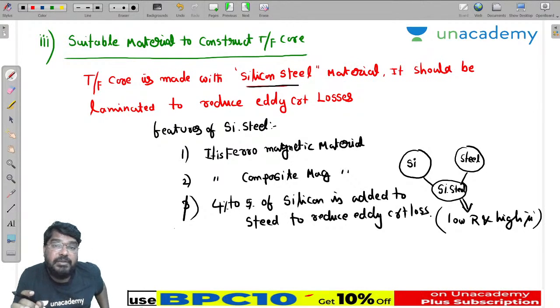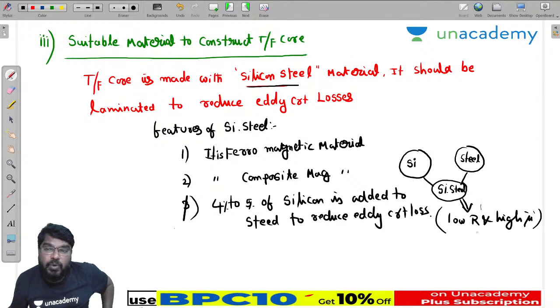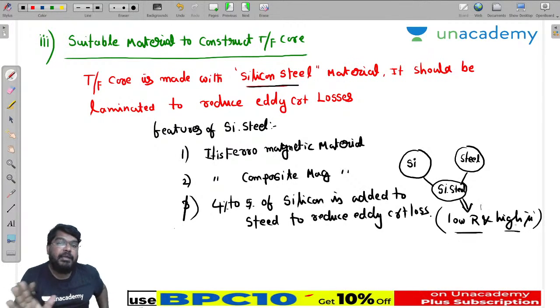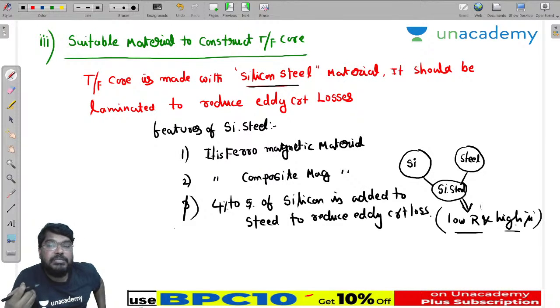Yes, lamination. We have two methods to reduce the eddy current losses. One is that 4 to 5% of silicon is added to the steel. Ferromagnetic material offers low reluctance and high permeability, that's why we use composite magnetic material. How much percentage of silicon? That is 4 to 5%.